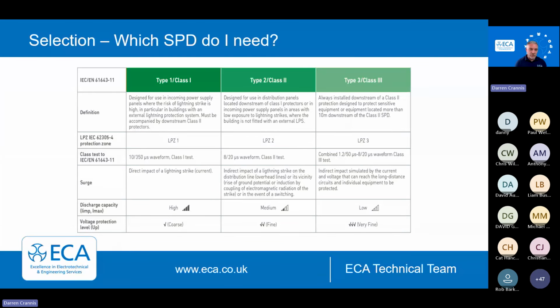So those Type 1 devices are in LPZ 1, so direct lightning strike. We're really looking at Class 2 or Type 2s. That's where most of our installation sits. Type 3s are typically built into equipment. So predominantly we're looking at Type 2s in our distribution boards.